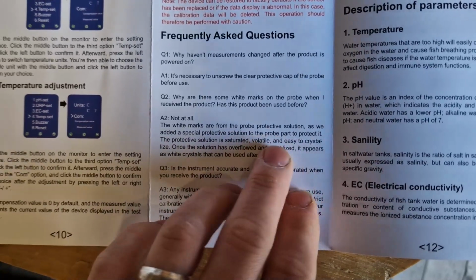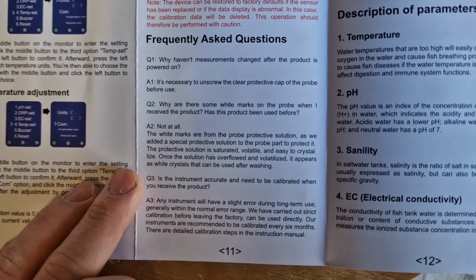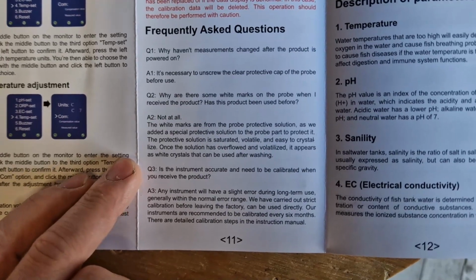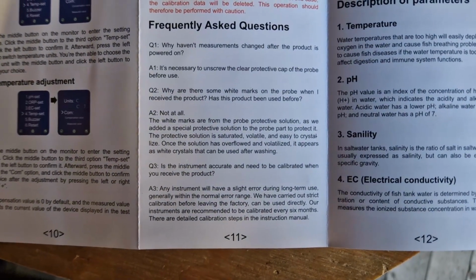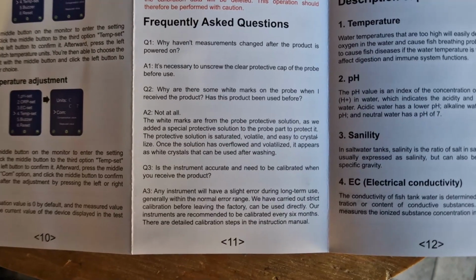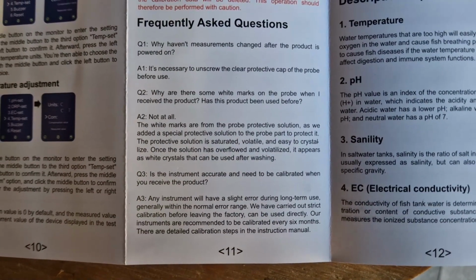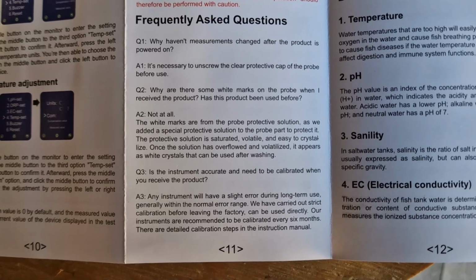Answer: not at all. The white marks are from the probe protective solution, as we added a special protective solution to the probe part to protect it. The protective solution is saturated, volatile and easy to crystallize. Once the solution has overflowed and volatilized, it appears as white crystals that can be used after washing. So if you do buy one of these and you notice any whiteness on the probe, there's nothing wrong with it. It just wants washing, cleaning off. It's just from the storage solution that's in the cap. So just clean it off, wash it, and you can use it. It's no problem at all.